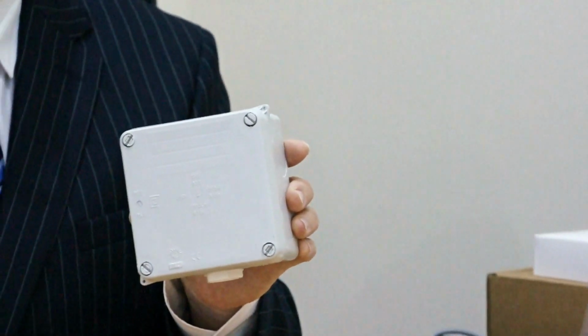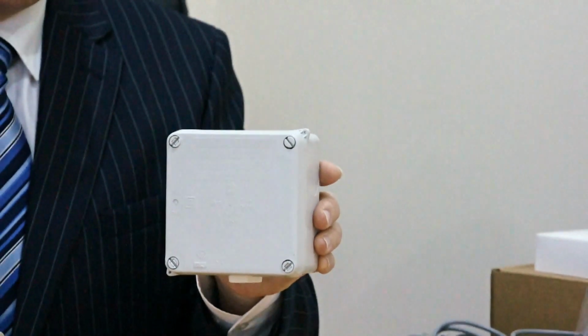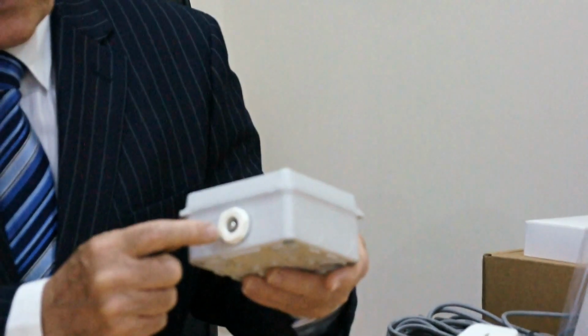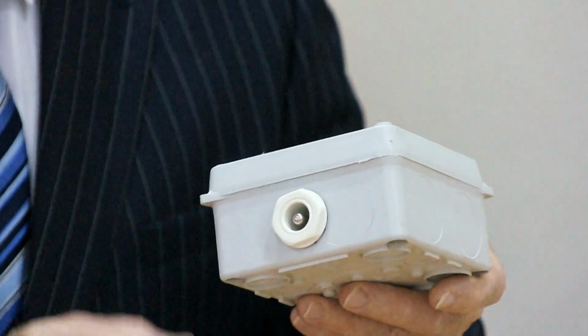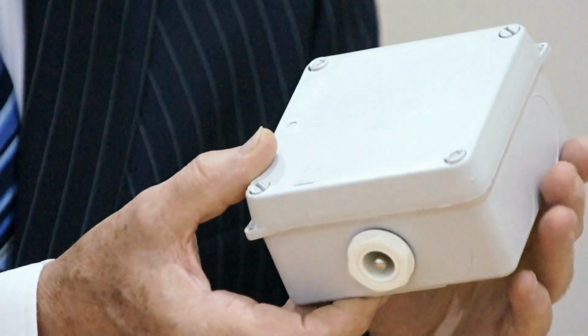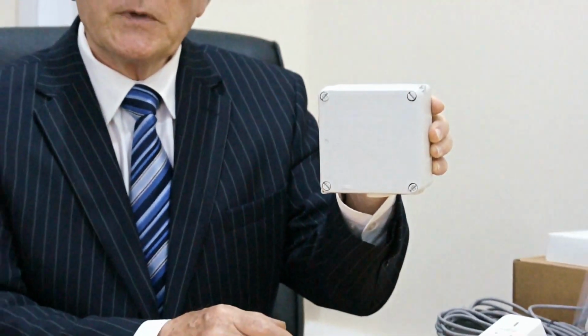So what sort of sensors and equipment do we have? The first thing we're going to look at, which might sound a bit odd, is the outside temperature sensor. This unit doesn't look wonderfully attractive, probably good really, because we don't want anybody to touch it once it's installed. This is fitted to an outside wall, and you'll notice there's a stainless steel probe sensor at the bottom, mounted so that rainwater will drip off the bottom without touching the sensor, because one thing we don't want to measure is evaporation loss of rainwater. What we want to measure is the actual outside air temperature.